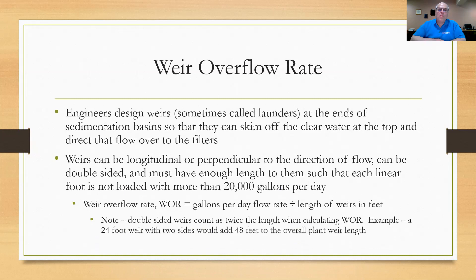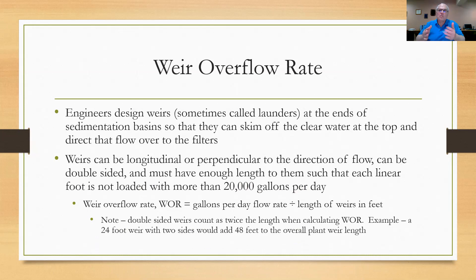Note that if you have a double-sided weir, which sometimes shows up on exams, the weir counts as twice its length since it has two sides. For example, if you have a 24-foot length of weir that has two sides pulling water from it, then it's actually 48 feet of weir length — so bear that in mind.